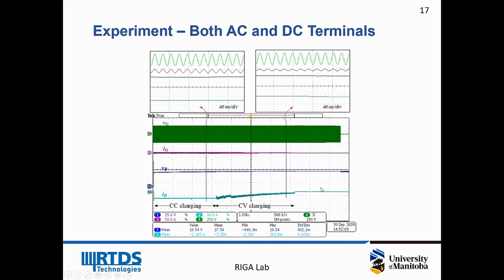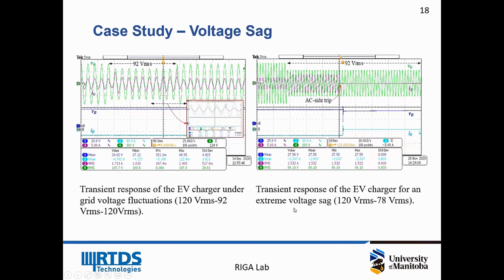We also can use the power hardware-in-the-loop system to study some power quality issues. For example, here is one case study. When the grid voltage decreased from 120 volts to 92 volts, that means there is a voltage sag for around 10 cycles, and the EV charger increased the grid current to maintain a more or less constant power to charge up the battery. When the voltage returned to normal, the EV charger control loop reduced the input current to maintain the same power as well.